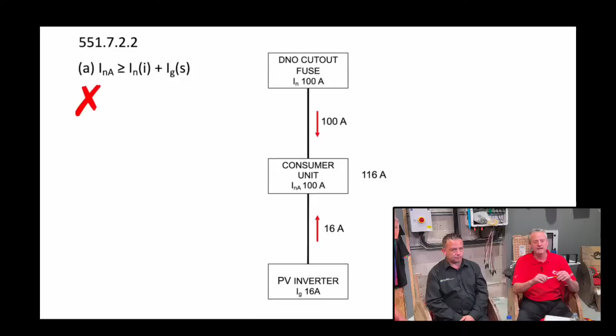So is there a workaround if that is what you've got? Yes, there is. Now, this is another one that's shown incorrectly because, as you can see there, whilst we've connected the PV inverter, we haven't connected it upstream of the protective device, so we can still get 116 amps to that consumer unit.